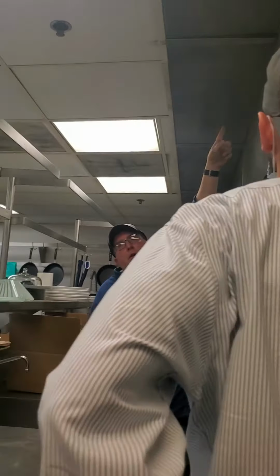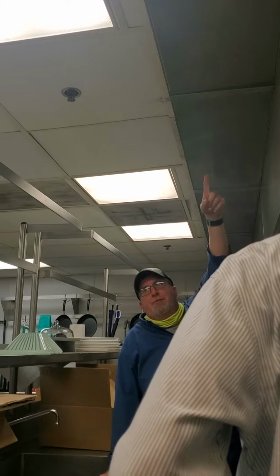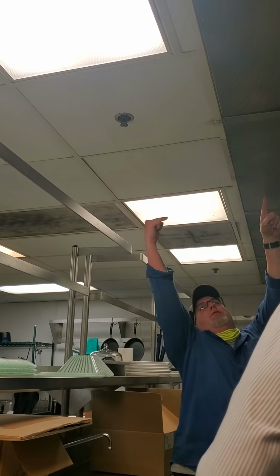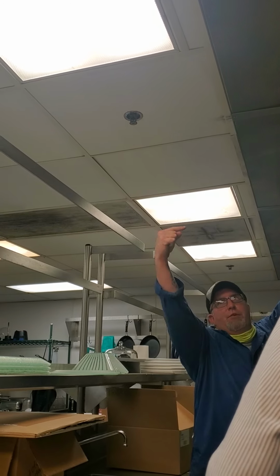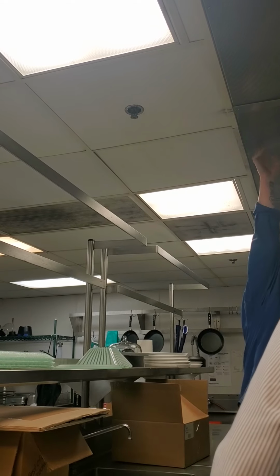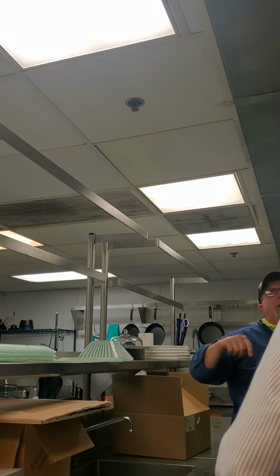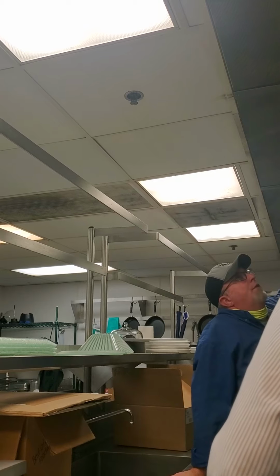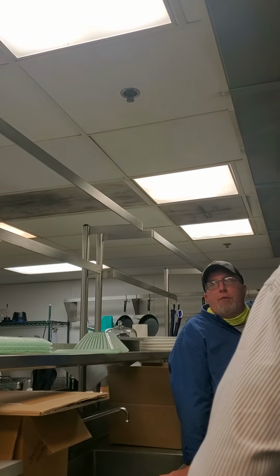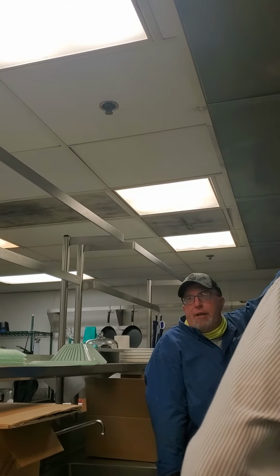This here is like almost 100% plugged. These diffusers - to take these out, the ceiling grid is screwed into the side of them. These things come down, they got to be power washed and put back up. And they haven't been, because they never wanted to take the ceiling down, and it'd have to be done in the middle of the night, and they didn't want to pay for it.